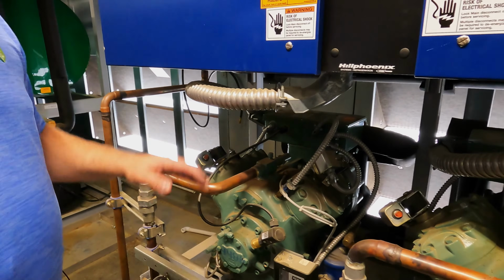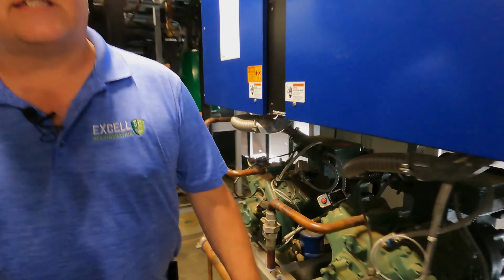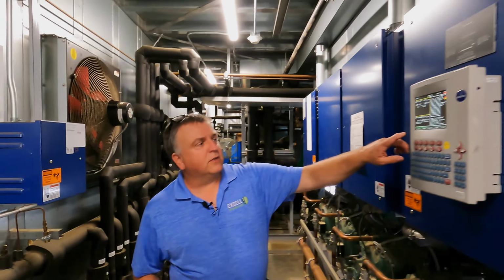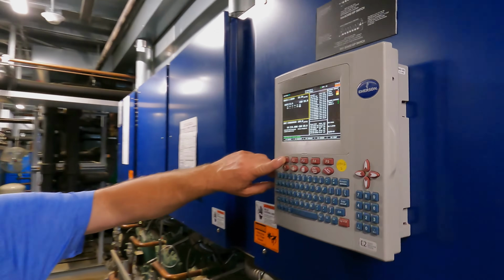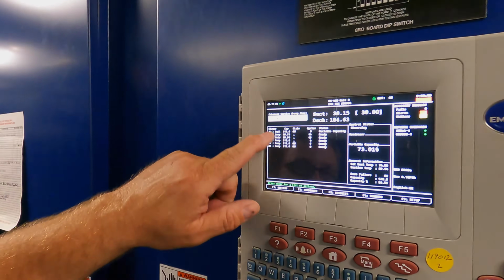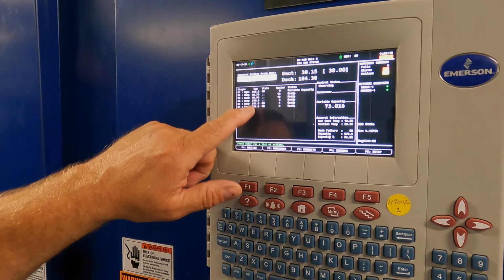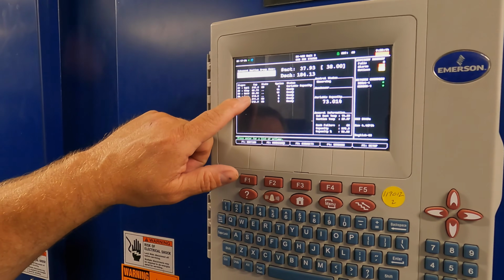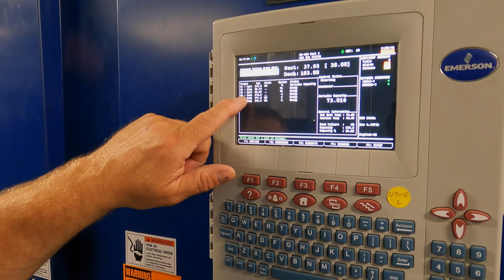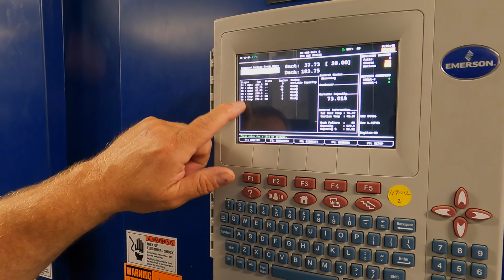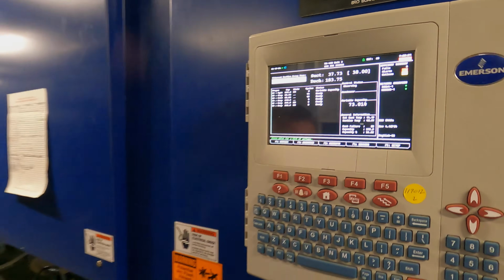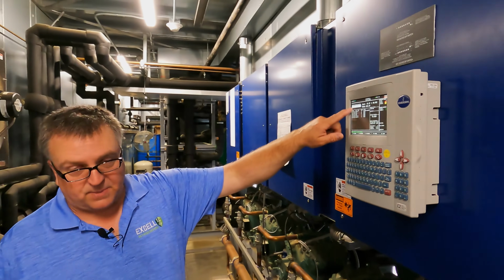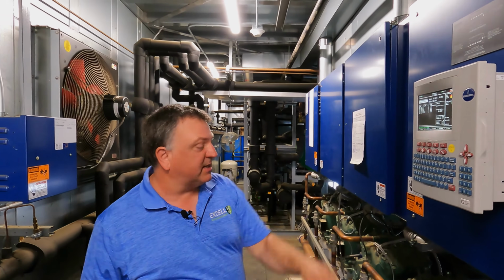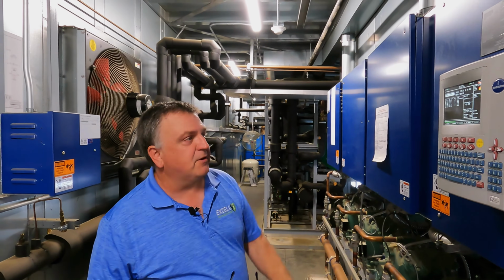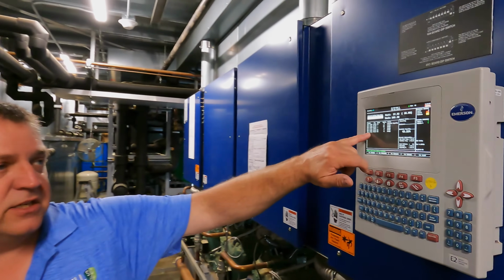This one, if you notice, has two. Now the reason they use unloaders, I'll show you here, is the stages on our compressors. If we go to our suction setup, you can see our stages. We have a digital compressor 1, compressor 2, unloader for stage 3, compressor stage 4, stage 5, and stage 6. Some guys get confused when they see this because they're not paying attention that it's stages, it's not compressors. We have 5 compressors, we have 6 stages.